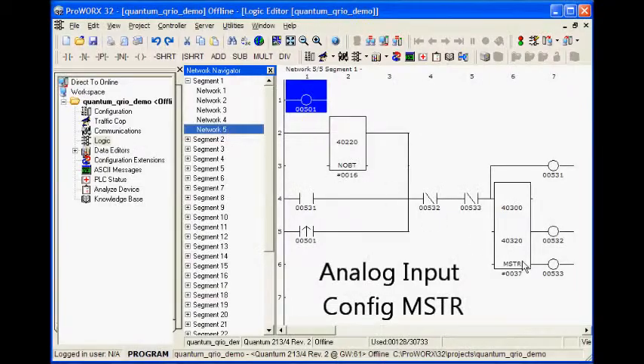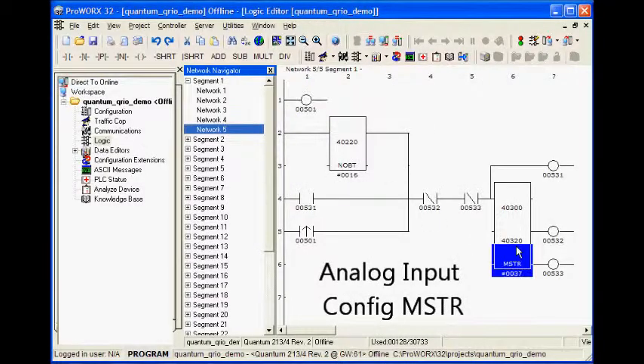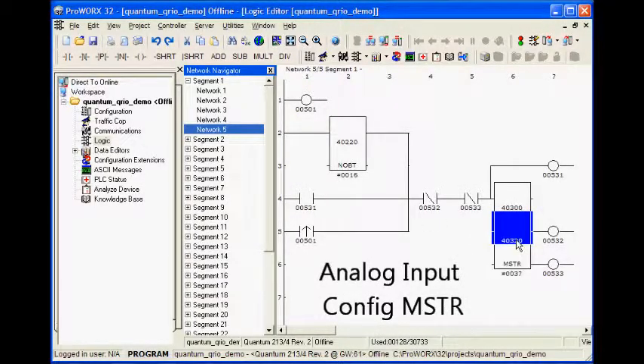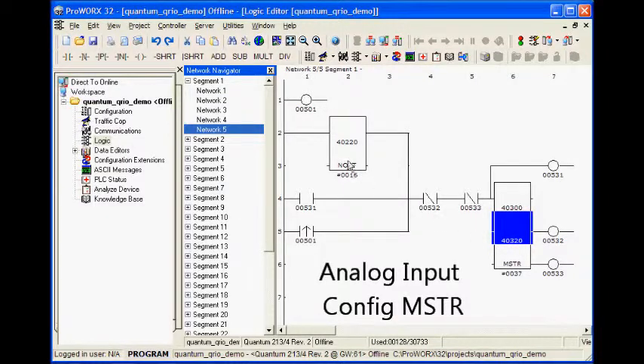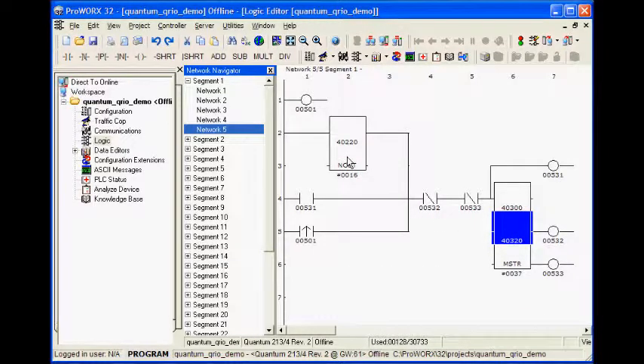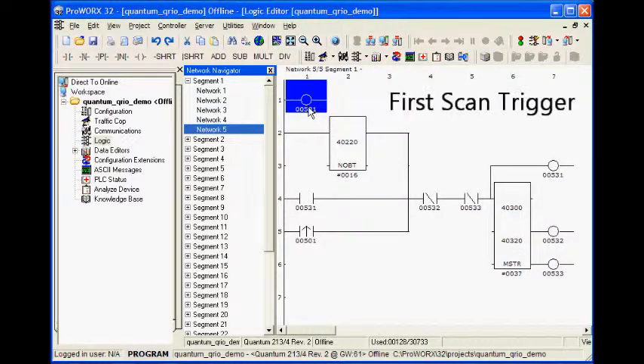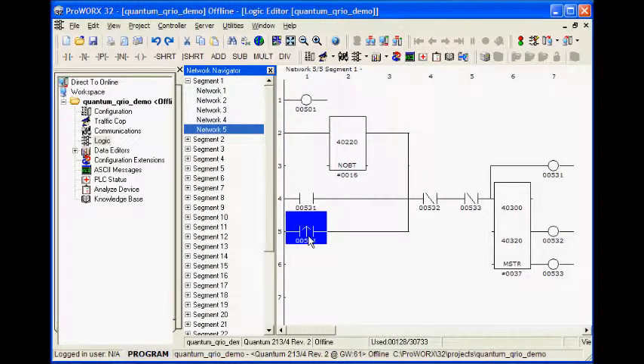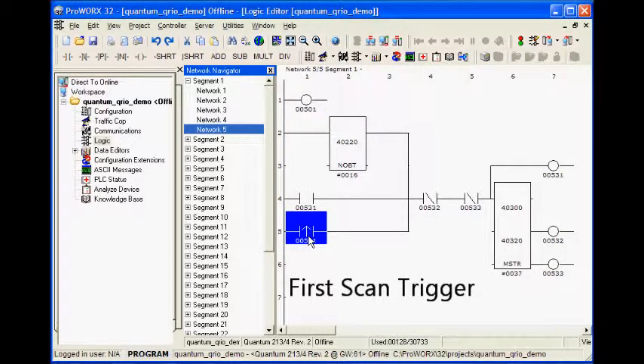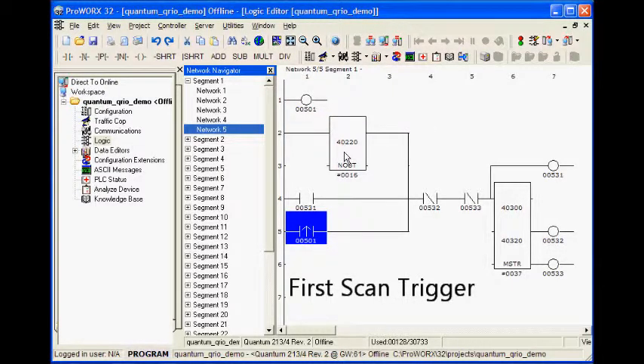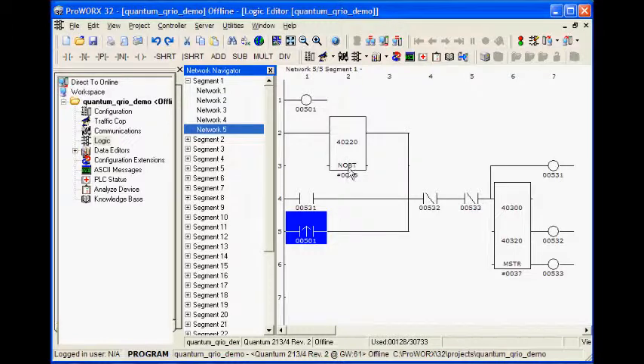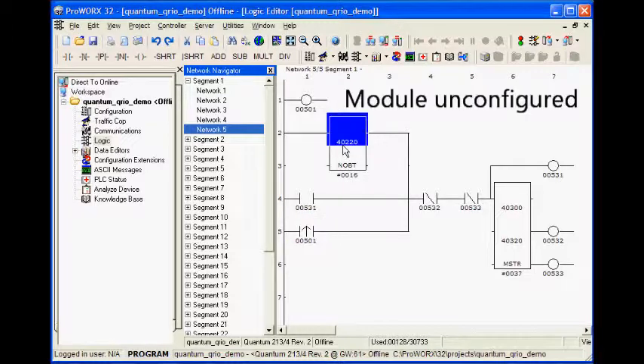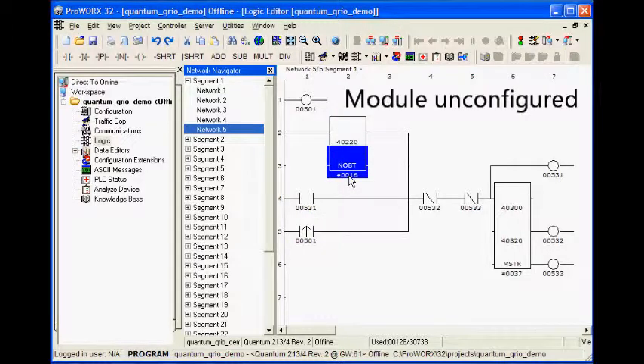This particular analog input card requires configuration. Network 5 is the MSTR used to configure the card. Coil 501 triggers the configuration each time the quantum program is reloaded. The NOBT block lets the analog card itself request reconfiguration using a bit read in the MSTR from the previous network.